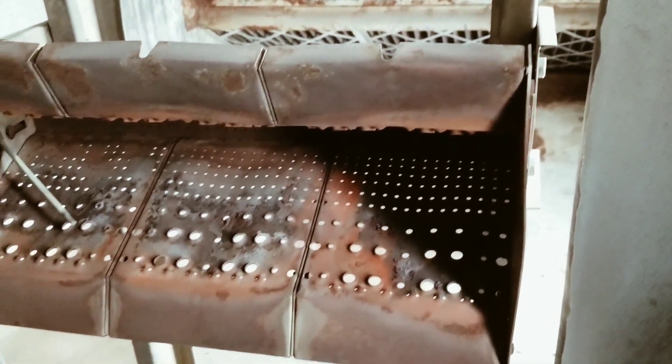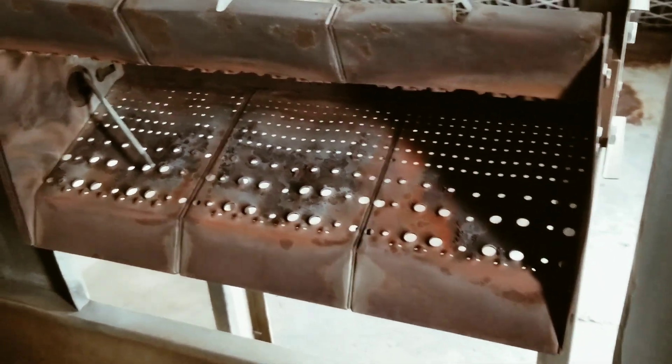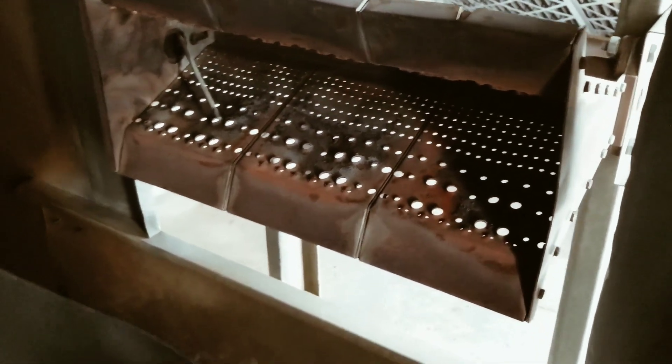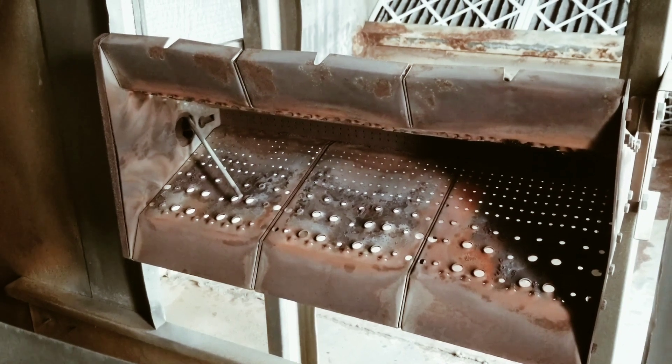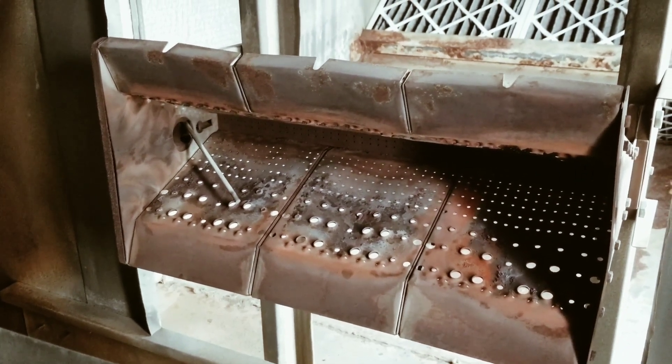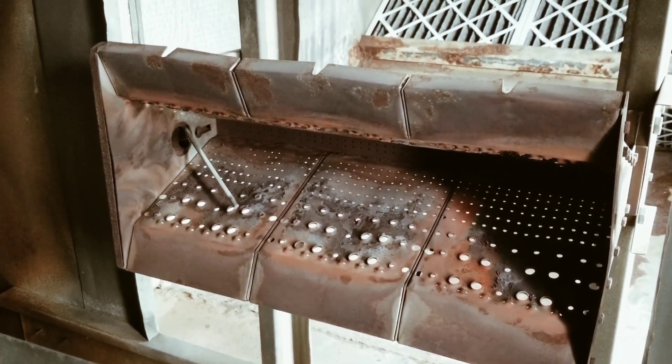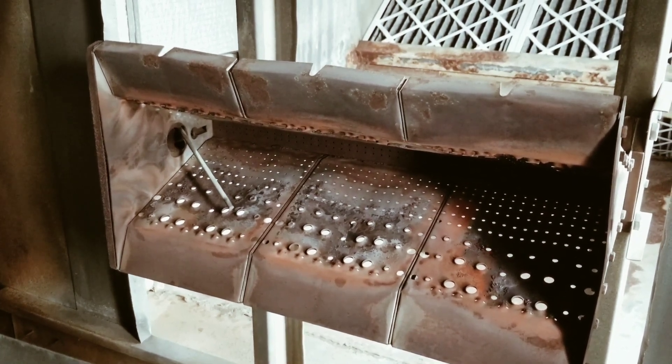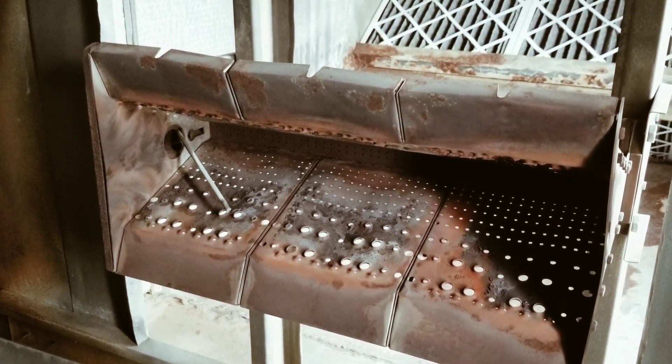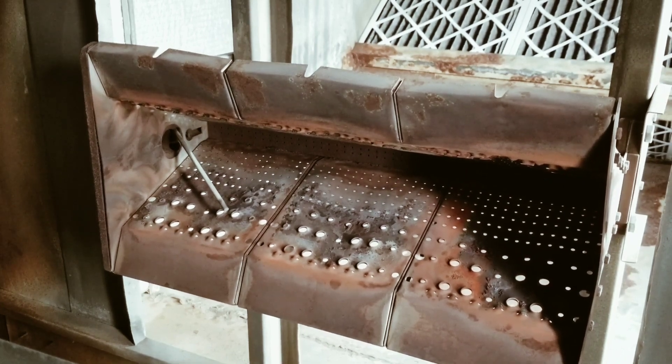If we come forward a little bit, we have the burner. This is direct fired. What does that mean? Well, that means that when this burner fires up, all the products of combustion are dumped inside the space. That's the way this runs. Indirect fired is when you use a heat exchanger. Direct fired is when the burner is directly in the airstream.